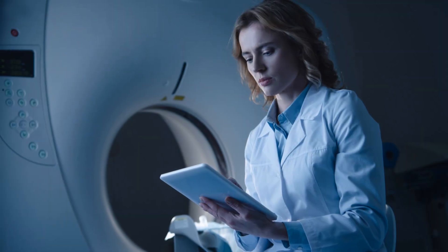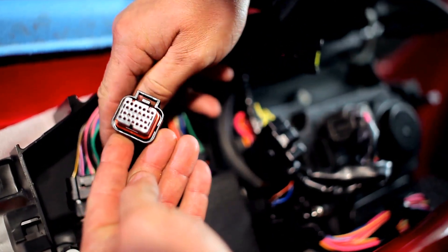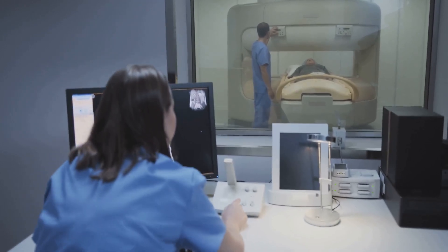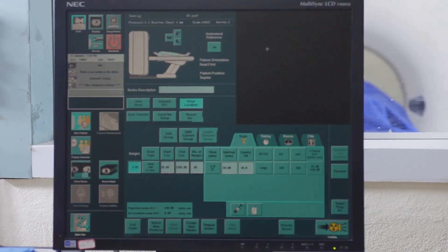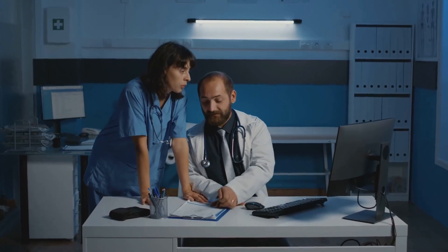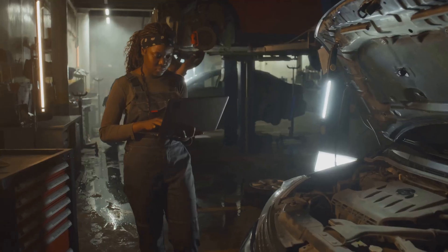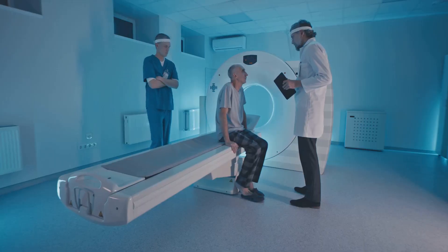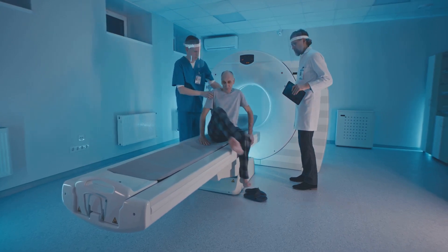The first step in diagnosing a CT scanner problem is a thorough visual inspection. This involves checking for obvious signs of damage, loose connections or wear and tear. Pay close attention to cables, connectors, cooling systems and moving parts within the gantry. Simultaneously, access the system's error logs. These logs record any operational issues or malfunctions detected by the scanner's internal monitoring systems. Analyzing error codes and timestamps can provide valuable clues about the nature and location of the problem. Combining visual cues with error log data often helps narrow down the potential problem areas, guiding further diagnostic steps and focusing on specific components or systems.